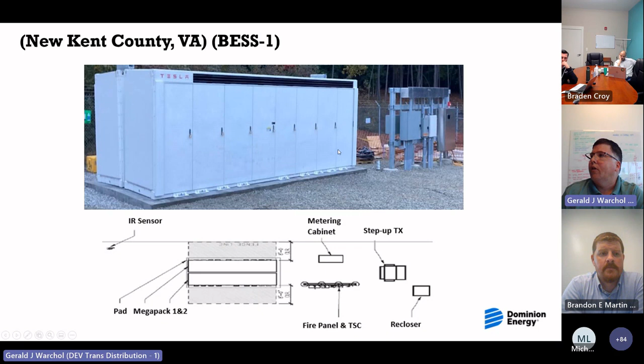A great shot, but essentially what we have going on at the correctional substation is there's a 20 megawatt solar plant on one of the circuits out of correctional. We coupled the battery in parallel with that. The problem is if there's not enough native load on this circuit B to consume the megawatts of the solar facility, you essentially see backflow happening up through the substation transformer.